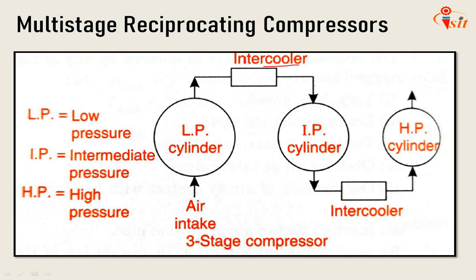This reduction in temperature means a reduction in internal energy of the delivered air, and since this energy must have come from the input energy required to drive the machine, this results in a decrease in input work requirement for a given mass of delivered air. It is common to find machines with either 2 or 3 stages of compression. The complexity of the machinery limits the number of stages.